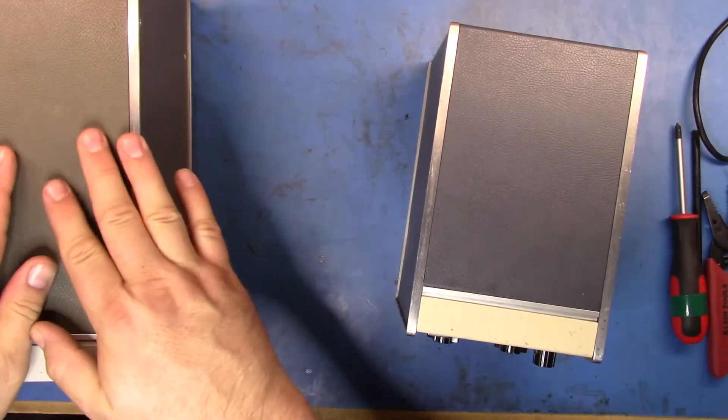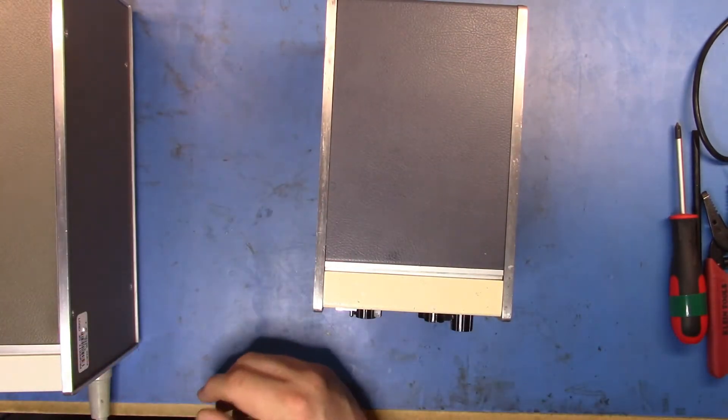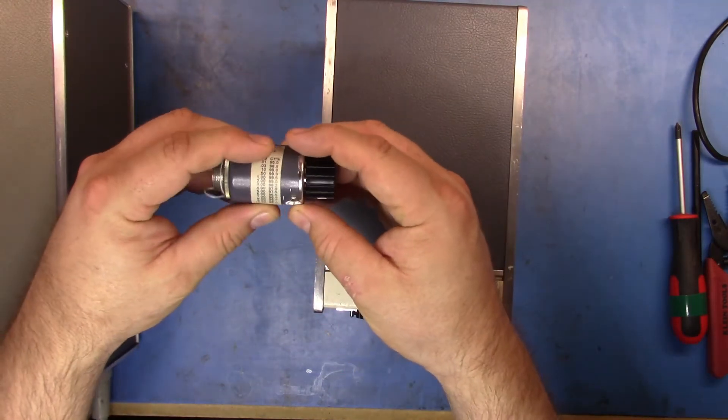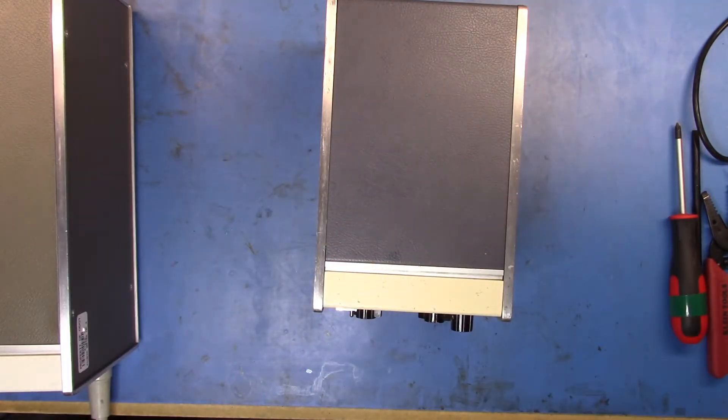Now, the 432A, the 431s, those series, the 432, I've been looking at a 432B as well which has a digital readout. They were all designed to utilize things like this thermistor mount here. These are closed-loop systems, so they can work without a power reference.